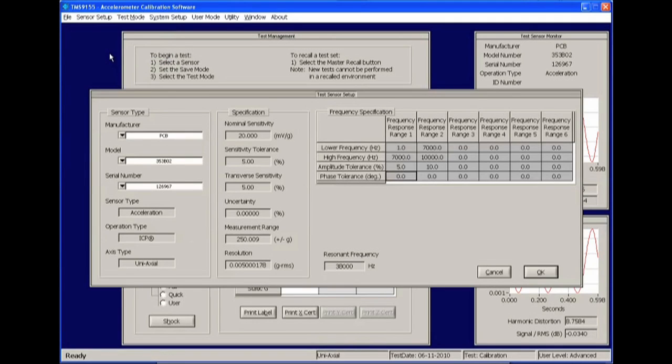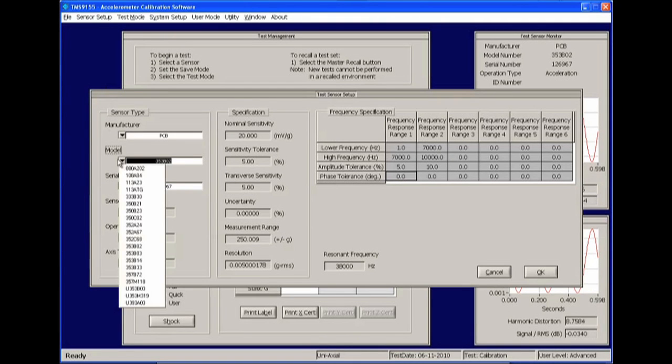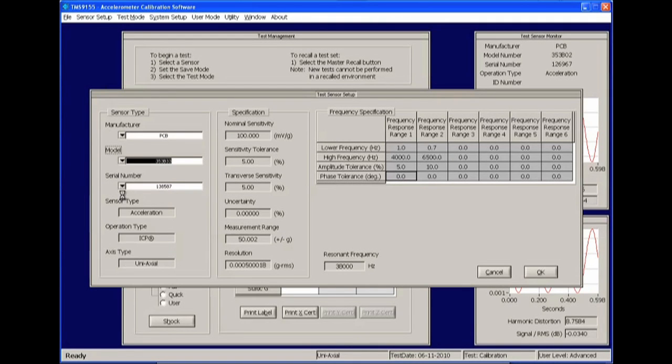Or from the main menu by selecting Sensor Setup, followed by Test Sensor. Once the Test Sensor Setup panel is displayed, select the manufacturer, model number, and serial number of the sensor being calibrated and click OK.